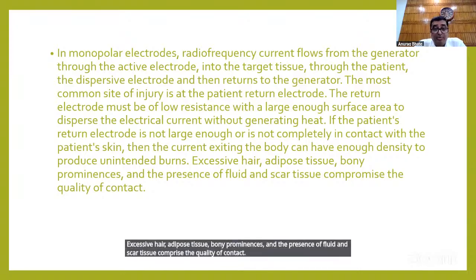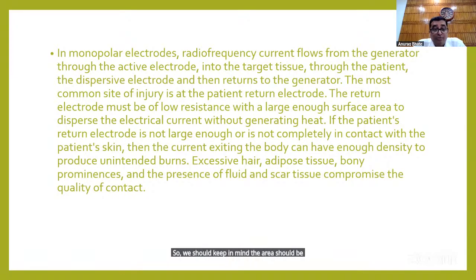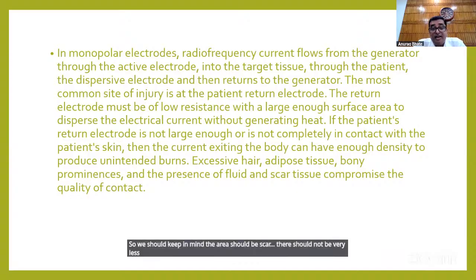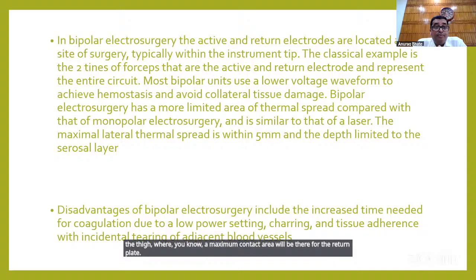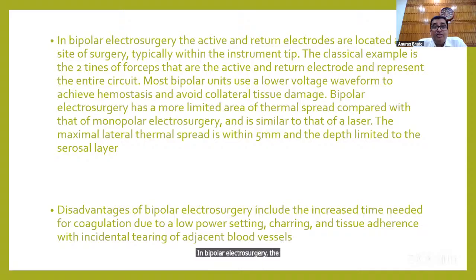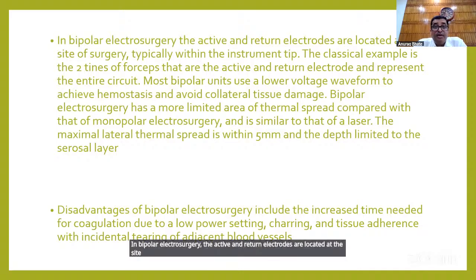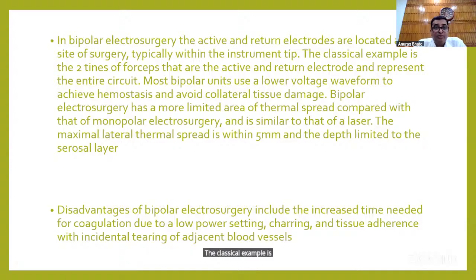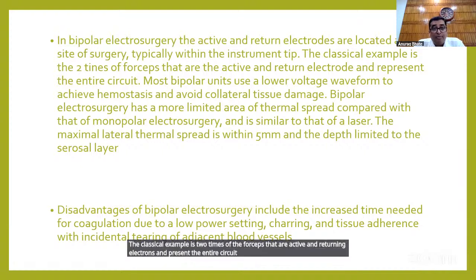So we should keep in mind the area should not be scarred. There should not be excessive hair. That is why most of the times we put it either on the back or on the thigh, where a maximum contact area will be there for the return plate. In bipolar electrosurgery, the active and return electrodes are located at the site of surgery, typically within the instrument tip. The classical example is 2 tines of the forceps that are active and return electrodes and represent the entire circuit. Most bipolar units use a lower voltage waveform to achieve hemostasis and avoid collateral tissue damage.